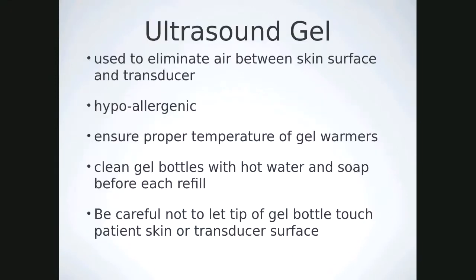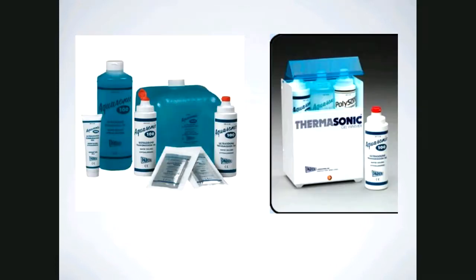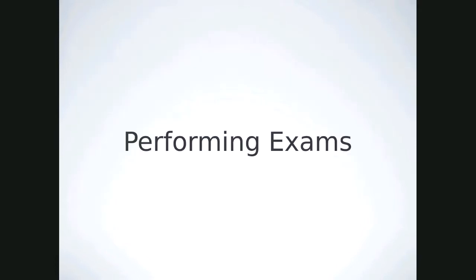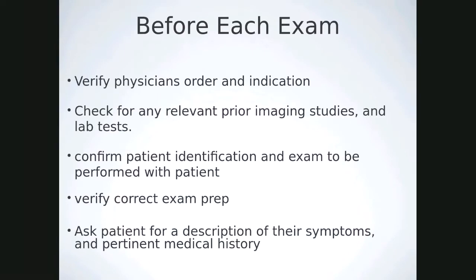Ultrasound gel is used to eliminate air between the skin surface and the transducer to promote transmission. We want to use something safe that doesn't cause breakouts and is at the proper temperature — not too warm, so it doesn't grow bacteria. Make sure to clean gel bottles with hot water and soap if refilling them, and be careful never to let the tip of the bottle touch the patient's skin or the transducer surface.